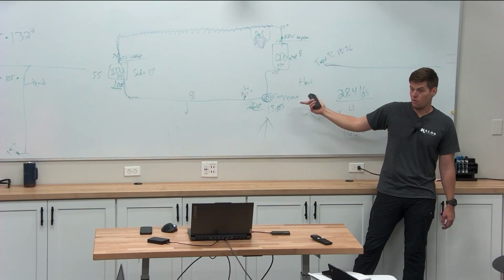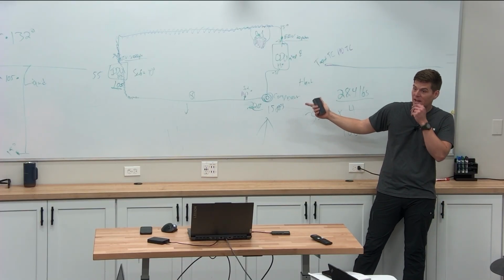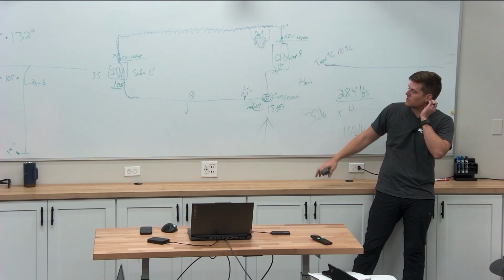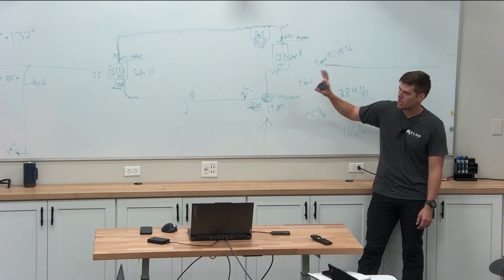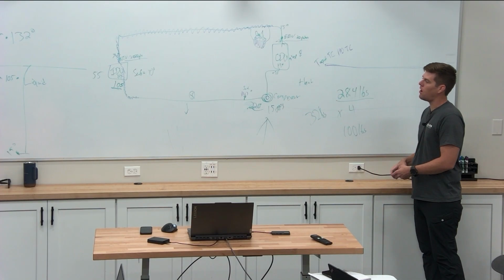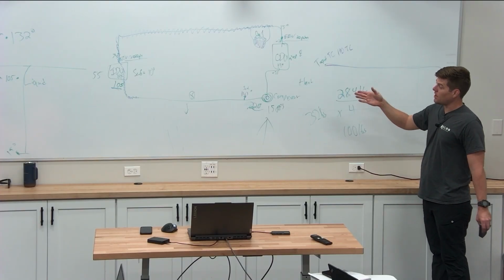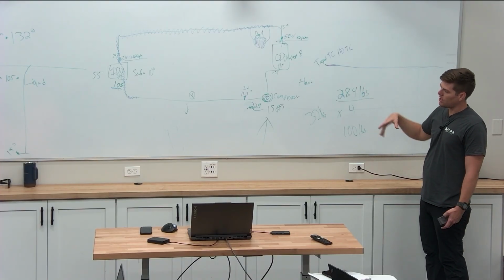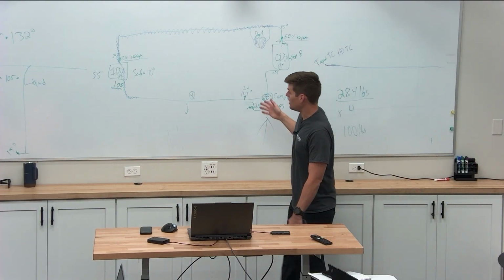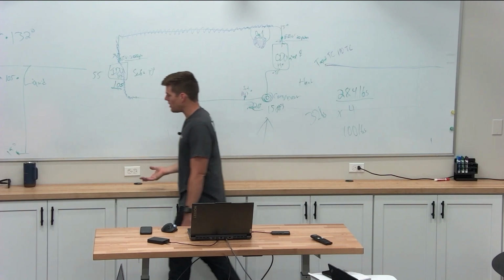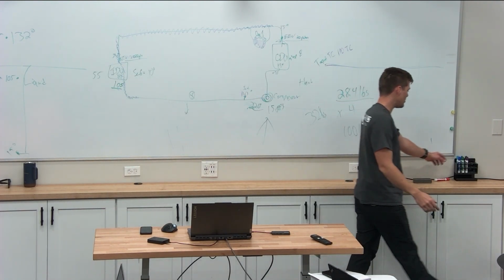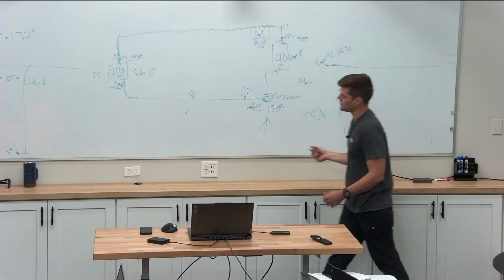This is severe overcharge. In a slight overcharge scenario, you'll see the same things, but less than this, and it's a little more difficult to determine. But this is severe overcharge. This is where they say the unit never worked right from day one. So you look at the data, plot it on the nice, pretty drawing that Roman made, and determine that it is really overcharged. And how do I know that? Because I did the subcooling math over here, and I found out that it's actually 95 degrees of subcooling.